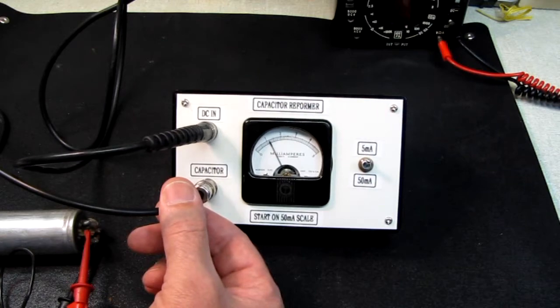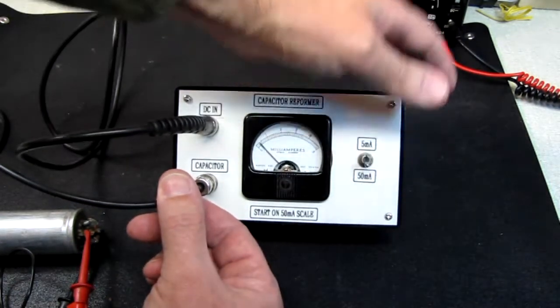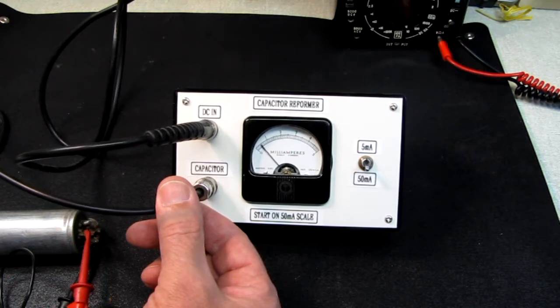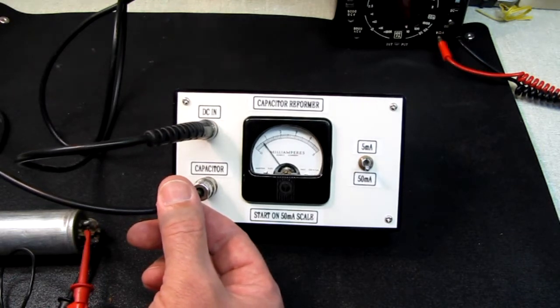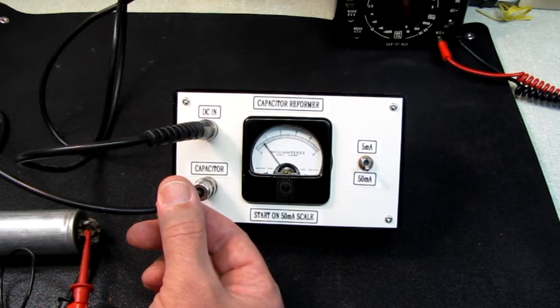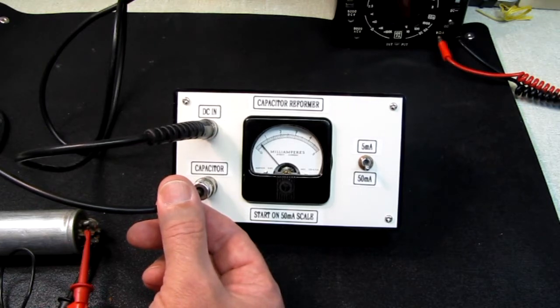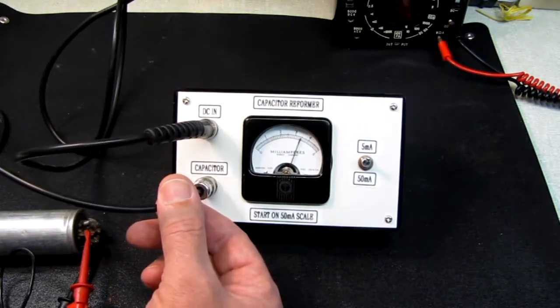So I'm going to let that sit right at that level for a few minutes. And now it's falling off. Let's go back up here. I'm going to bring it up to 300 volts. And again it's falling off. It's jittering around a little bit, settle down. We're under 5 milliamps. I'm going to let that sit.